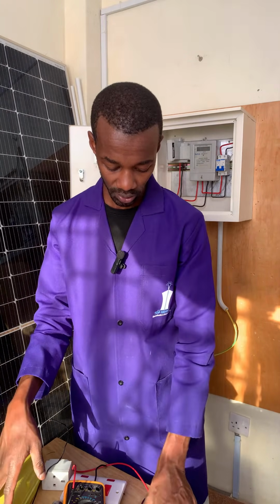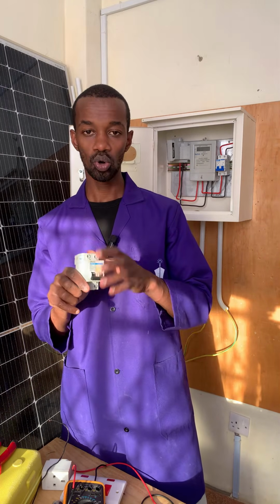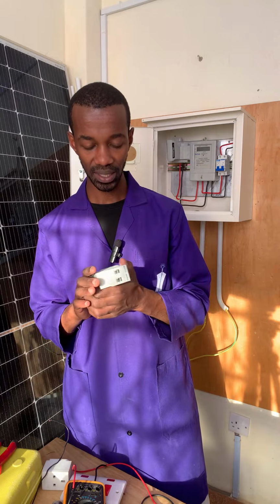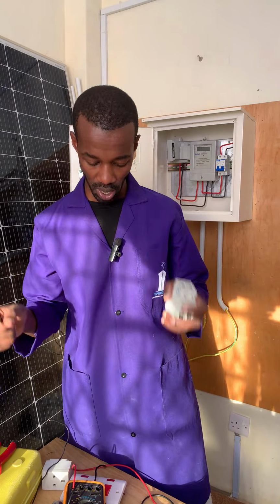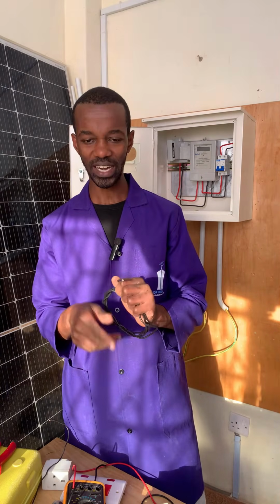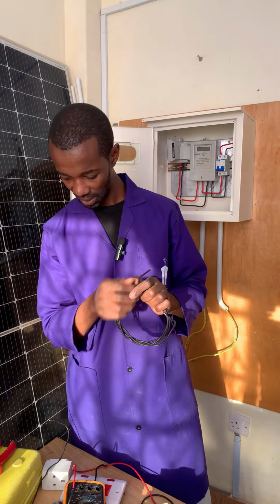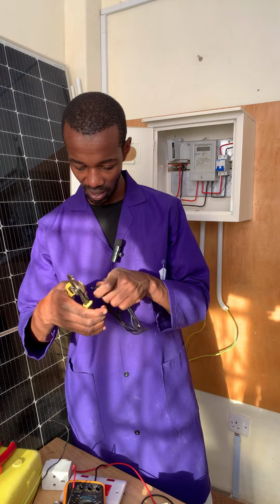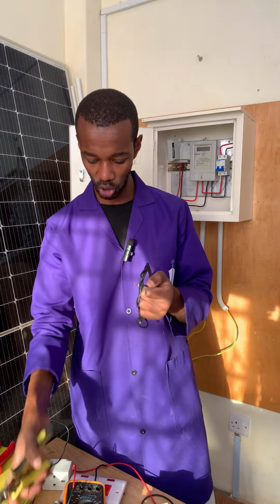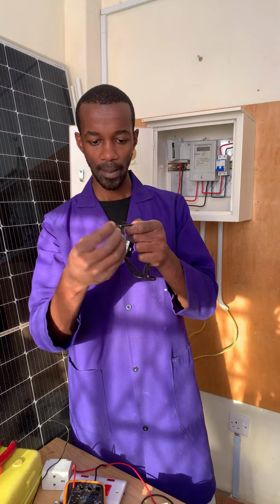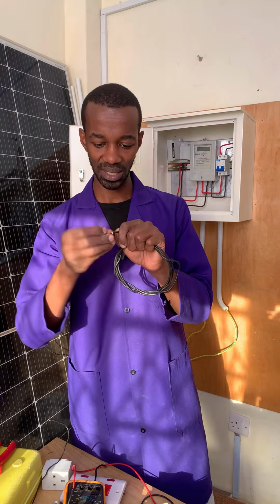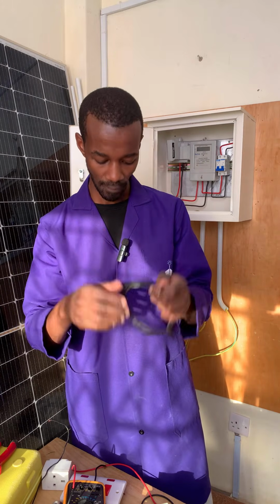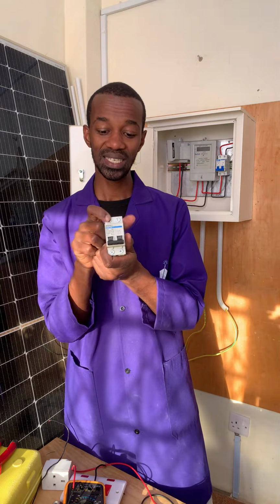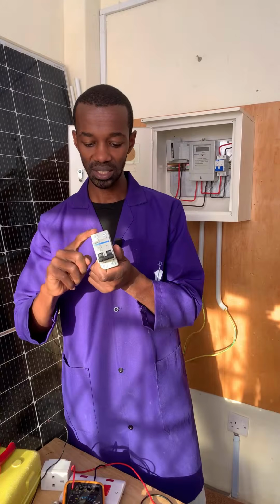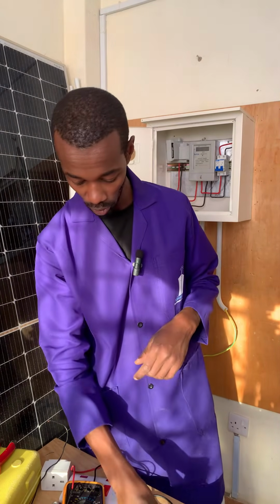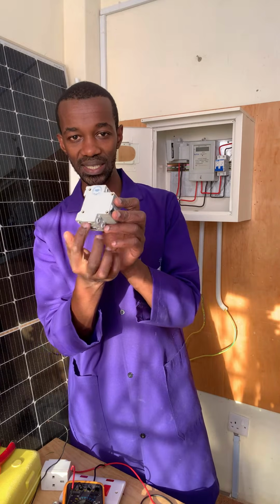Now, what you need to do, my top boss, is to ensure that you disconnect that power completely, especially at the meter box. Remove the mains cable. If they are charred, or if they have some oxidation on that wire, so you find that this is copper, but there is some green, rusty substance on the cable, as well as on this terminal here, it is time to do some cleaning, some maintenance, or do away with the entire double pole switch, especially if it has started melting the plastic around it.